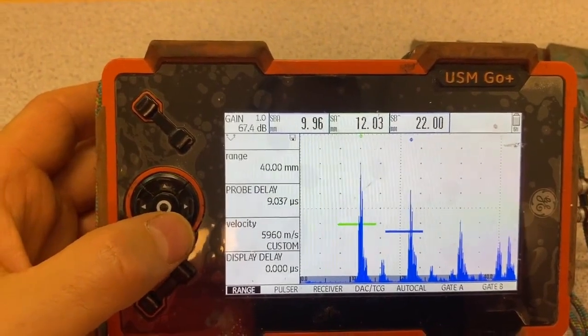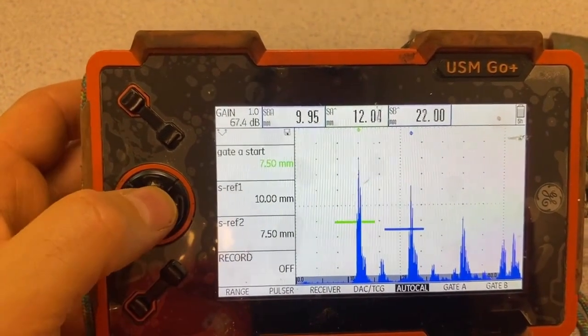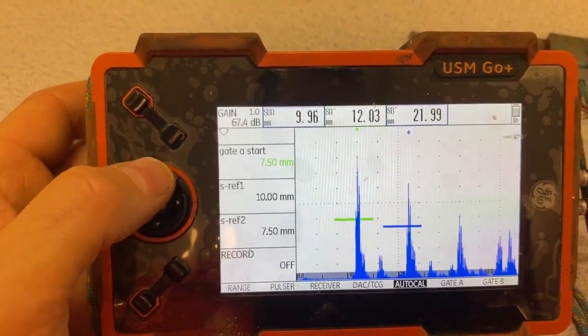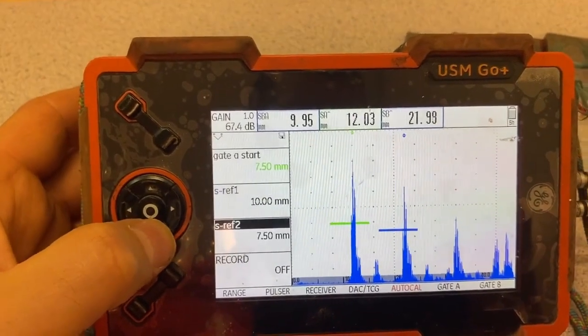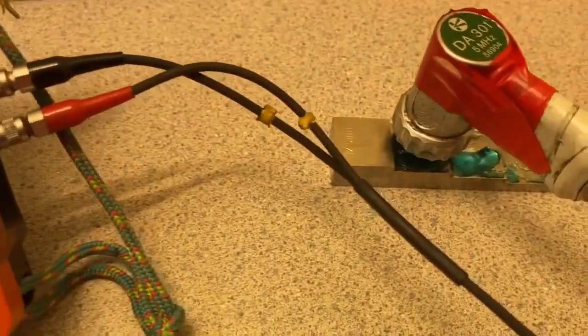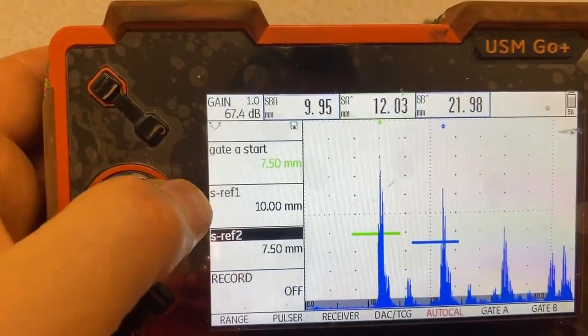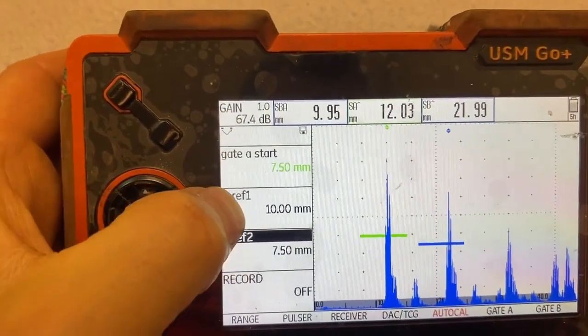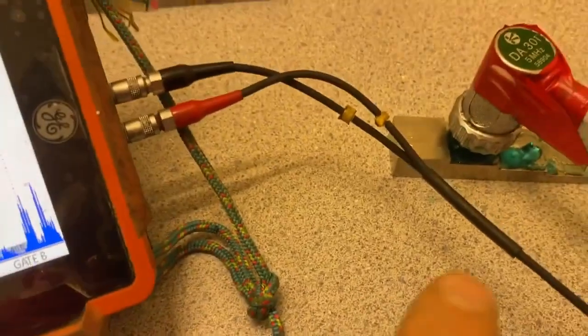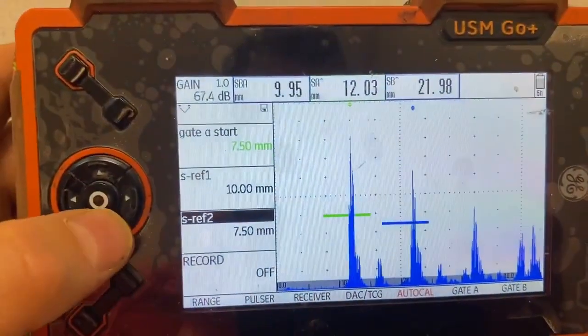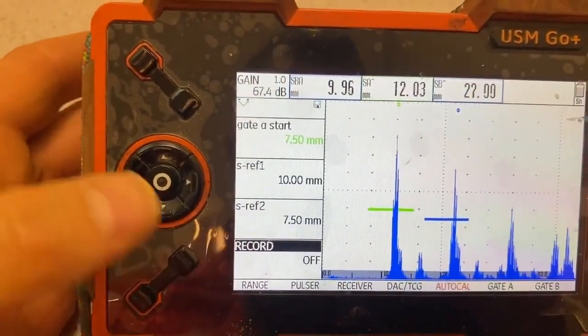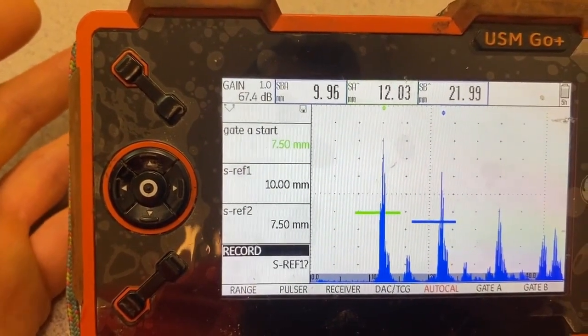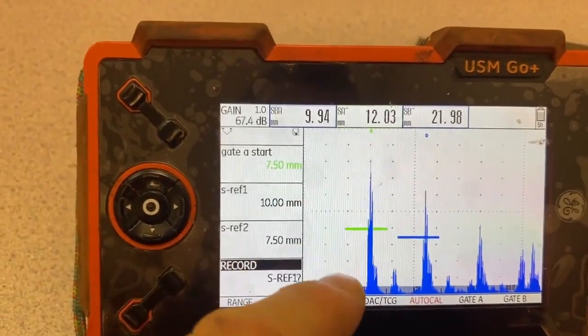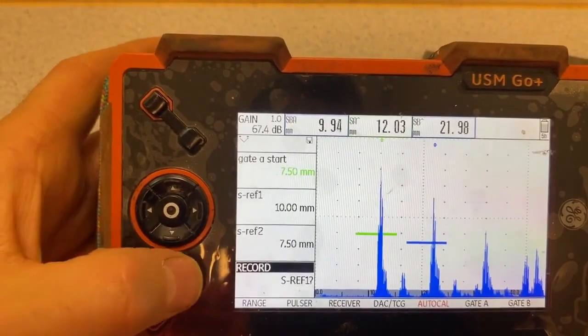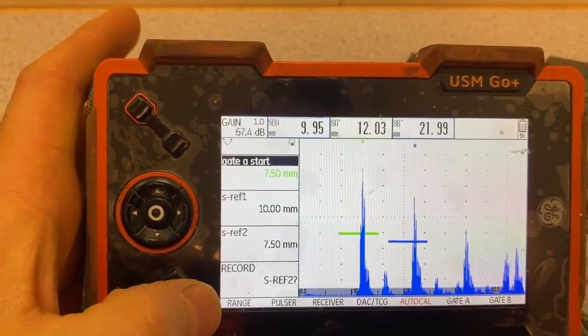Now it's 80% of the screen. And we need to start to record. Now we have 1 at 10. Here's 1 at 10 as reference 1, and reference 2 is 7.5. Now we need to start to record. We will press there, and now at this moment it is completely ready to record the incoming signal number 1. We press again there, it's recorded.